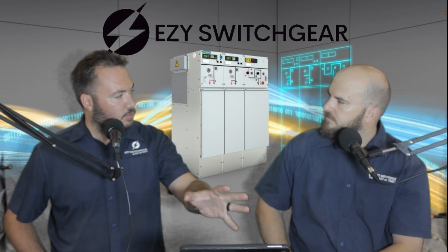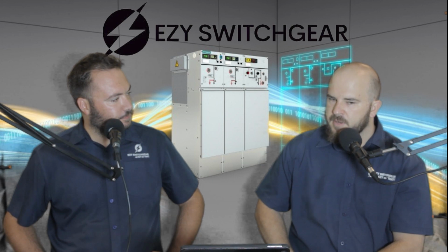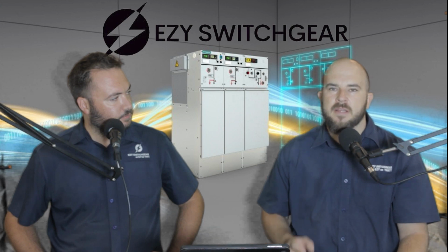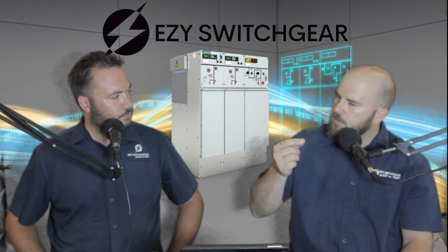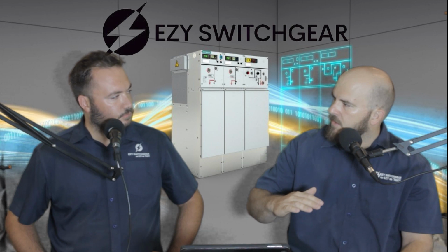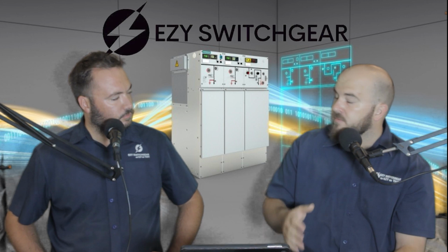Okay, great. And that also helps to protect the humans and the plant that it's feeding power to. That's correct. So when you set up your protection in your MV switchgear, you always set it up in such a way that it will adhere to the safety limits of your equipment. So let's say you have a piece of cable and the maximum normal rated amps that it can operate at is 200 amps. You're going to set your protection settings very close but below that. So that when it goes over that, you will then trip out to protect this cable, because if the cable starts getting hot, it will melt, the insulation will collapse and it will flash, and then you've got an outage.